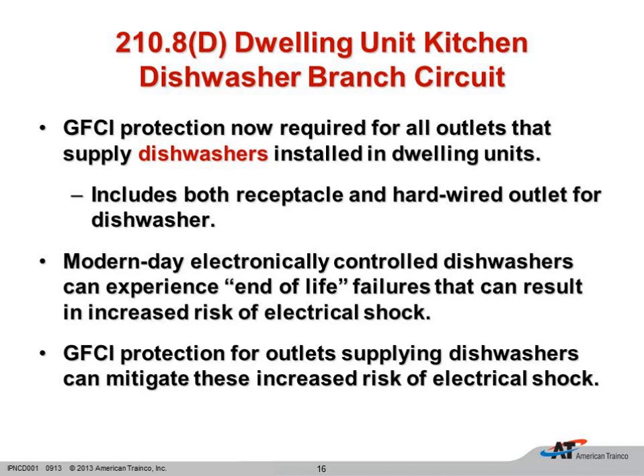GFCIs were first introduced into the National Electrical Code in 1971. We had approximately 625 electrocutions every year prior to that. Since we have increased the presence of GFCIs, both in dwelling units and in commercial and industrial buildings, those electrocutions have dropped to about 105 per year. So they definitely have an impact on safety, and we just want to make sure that they're going to be reliable, and we think, with the changes that were made, this should be a great little addition here.